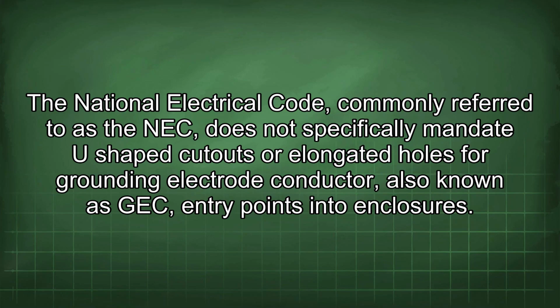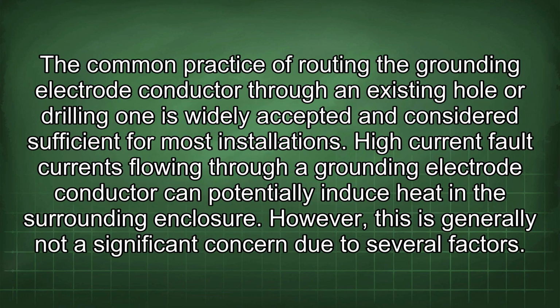The National Electrical Code, commonly referred to as the NEC, does not specifically mandate U-shaped cutouts or elongated holes for grounding electrode conductor, also known as GEC, entry points into enclosures. The common practice of routing the grounding electrode conductor through an existing hole or drilling one is widely accepted and considered sufficient for most installations.